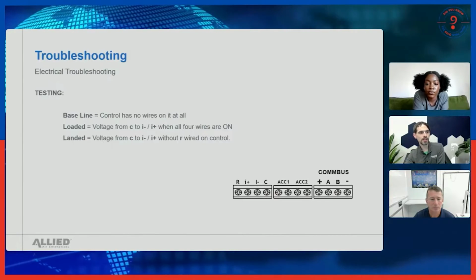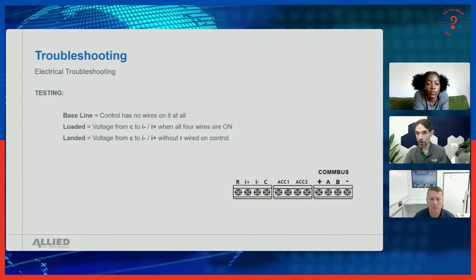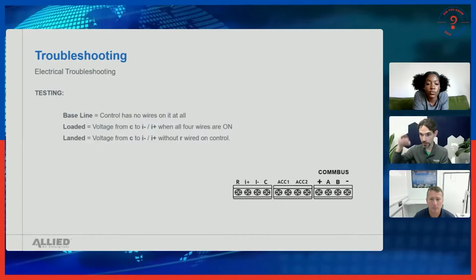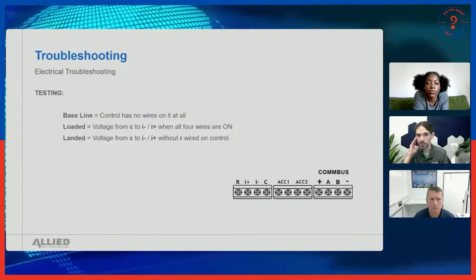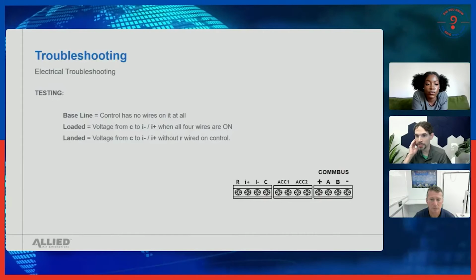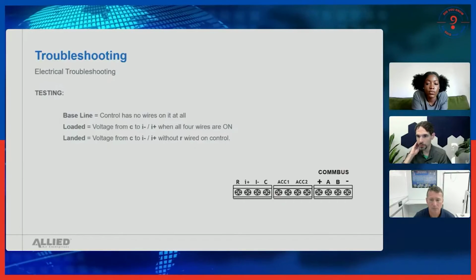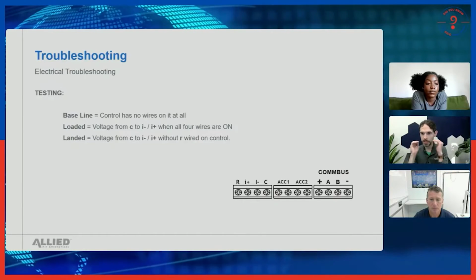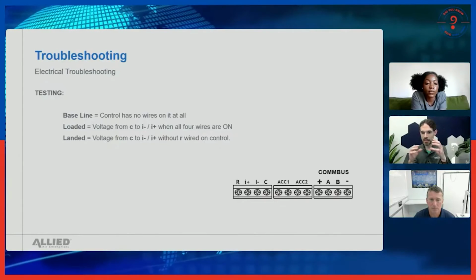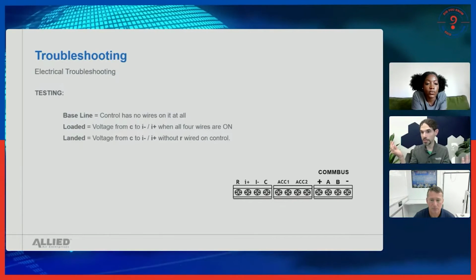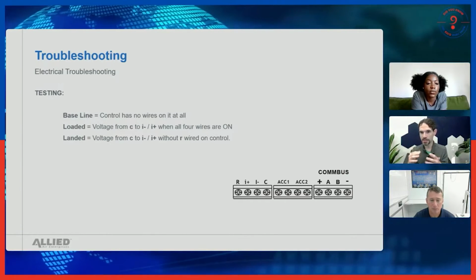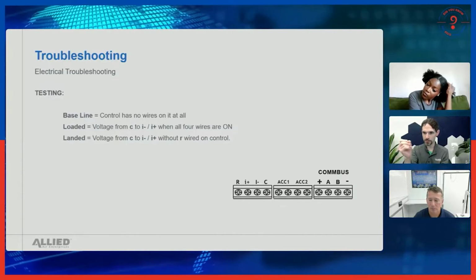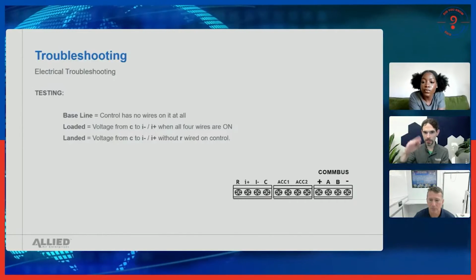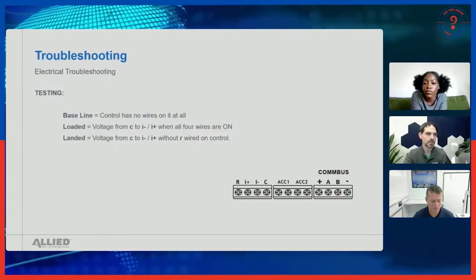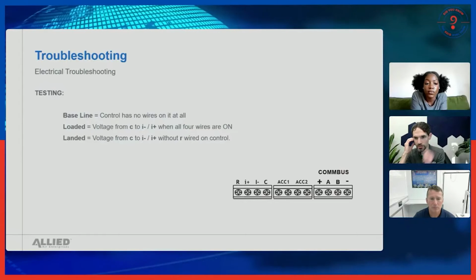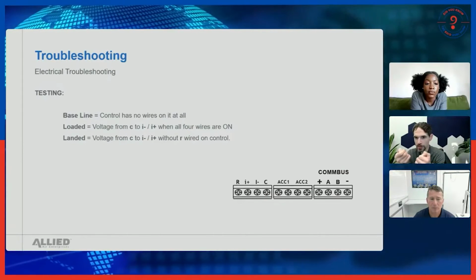Something else you can look at is when you actually have voltage on, how much voltage is going through. Are we having any loss? Is it fluctuating along the way? You can tell a lot from a system by looking at the power and how much it's fluctuating. With the inverter equipment we've got, we have different levels we look at, a high and low for voltage, and take corrective action if voltage goes too low or too high, whether it's a surge, a brownout, a blackout, something that's happened, and try to protect it. In the same way, you could sit and read the system, are we jumping drastically in voltage?